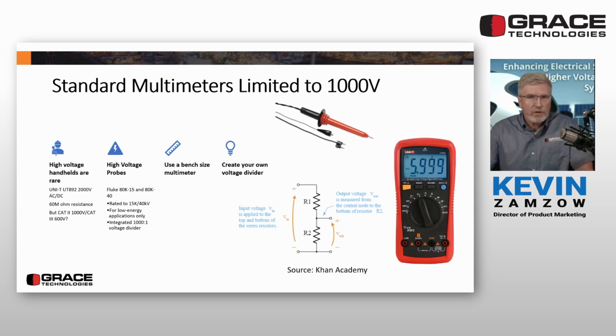As we have received requests to support DC voltages up to 2500 volts DC and have looked at designing a product to meet the request, we understand that most multimeters are limited to 1000 volts or less. The UNI-T UT892 is an exception with a 60 megohm internal resistance that allows up to 2000 volts use. Other options include using higher voltage test probes, for example, the Fluke 15 kV and 40 kV probes with an internal 1000 to 1 voltage divider, or designing your own voltage divider. We integrated a voltage divider in our new higher voltage DC safe test points so users can use standard voltmeters.